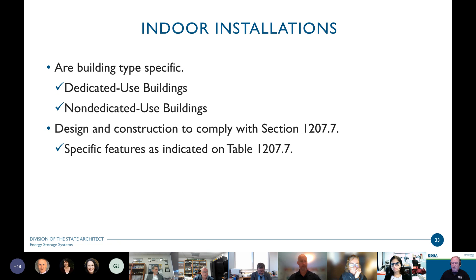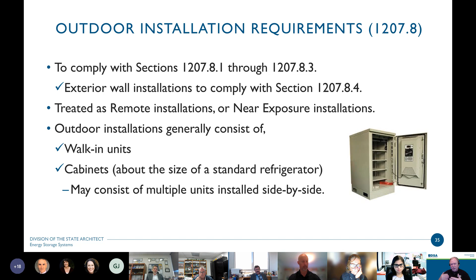So outdoor, we're talking about those installations that are going to be complying with sections 1207.8.1 through 8.3. And we're talking about exterior wall installations as well here. Those are considered outdoor installations, and those comply with section 1207.8.4. These are treated as remote installations or near exposure installations. The outdoor installations are generally going to consist of those big shipping container walk-in units. They could consist of cabinets like we see here in the picture, about the size of a big refrigerator. You put in cabinets or the walk-in units, they could consist of multiple units installed side by side. So you know, daisy chain these things together.